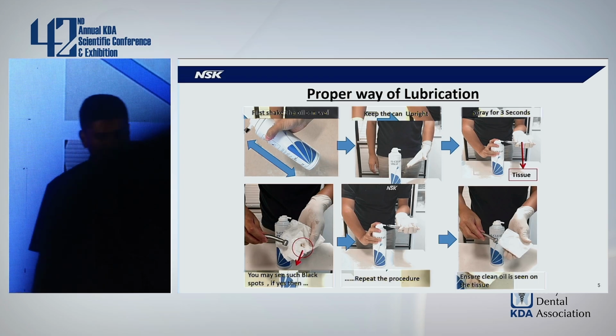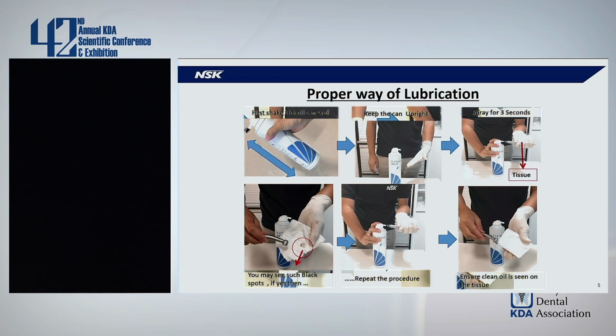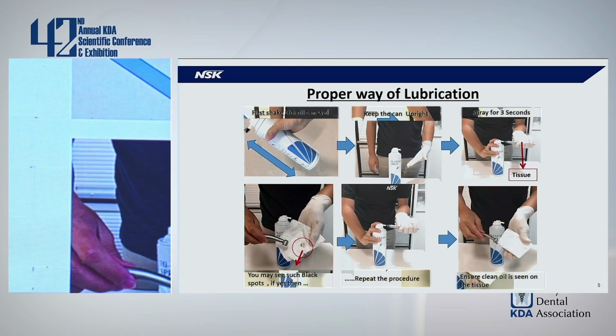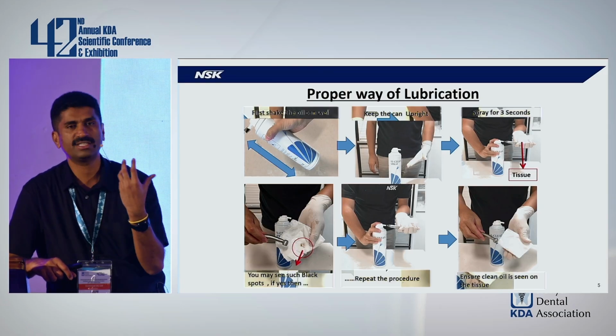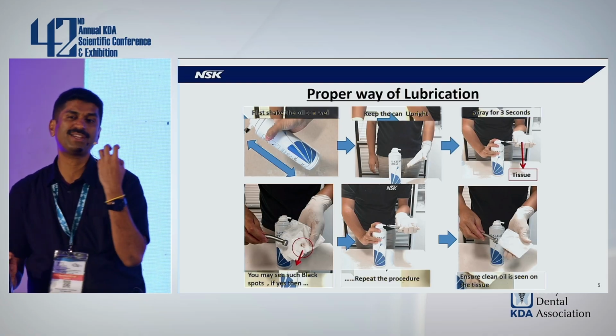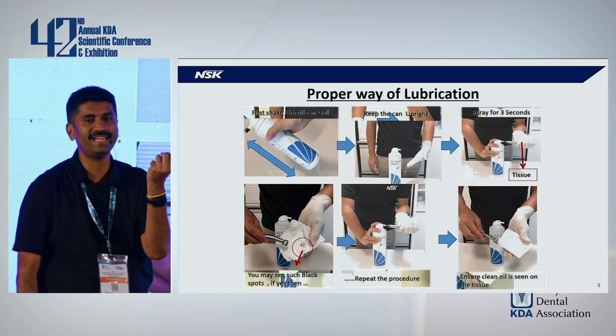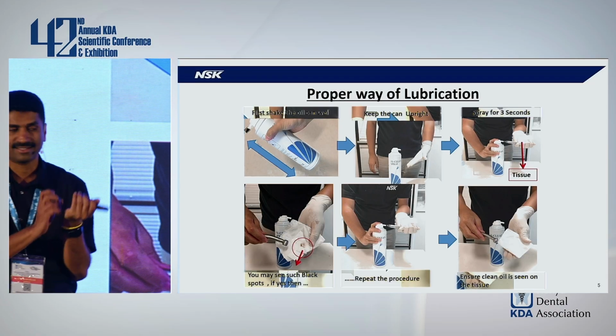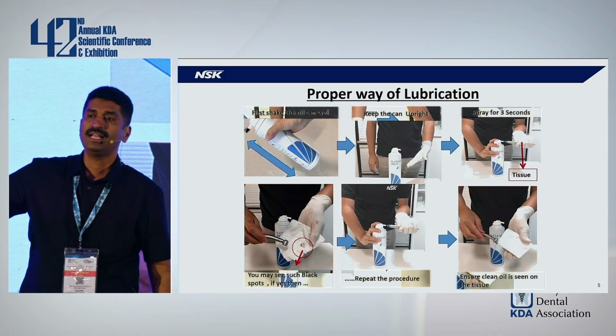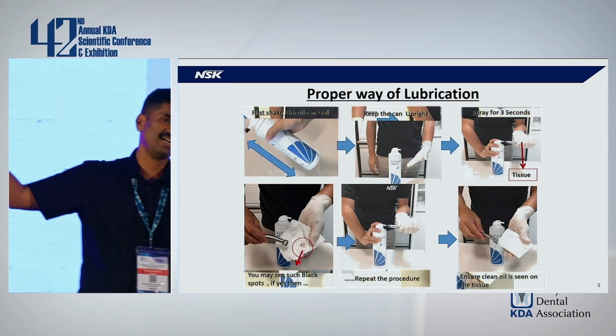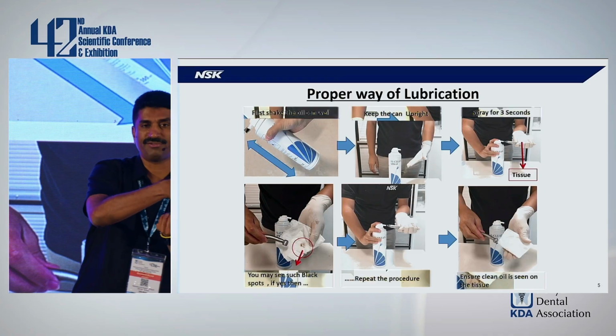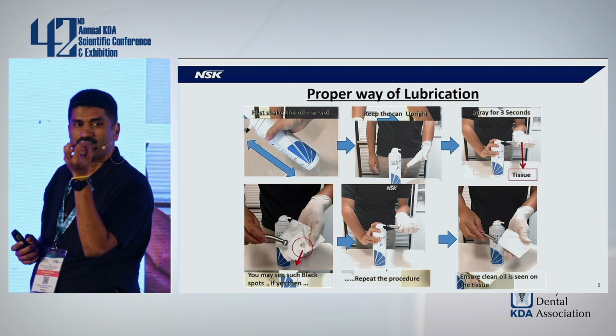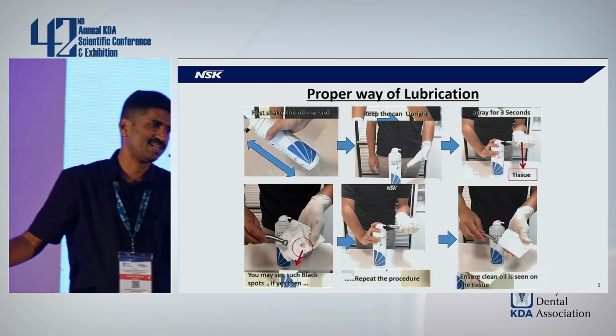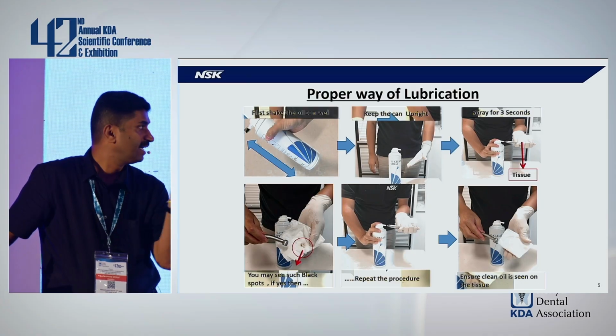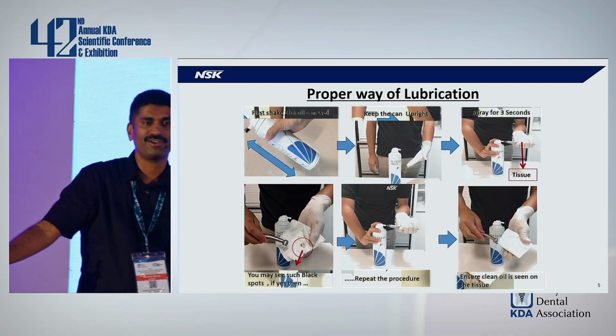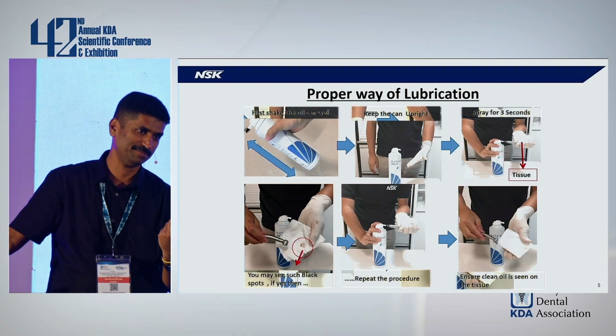It's very simple. The handpieces have something called ball bearings inside. And there is a non-metallic part, which in technical words we call a retainer, which is made up of a special type of plastic that holds the ball bearing intact. Now, if you do not lubricate and put the handpiece as it is into your autoclave, the 135-degree steam will come in direct contact with the inner part of the handpiece, and it will try to melt this special type of plastic, which is the retainer, and thus, after each autoclaving, the life of your cartridge goes down by 5 to 10%.